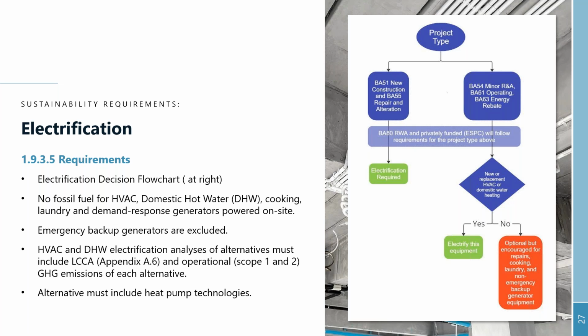Electrification is definitely a big change, so a lot more definition regarding when it's applicable. This flow chart that I'm showing is directly out of the P100, which really helps from how the project is funded to then understand, you know, what technologies are being replaced and when electrification is required.